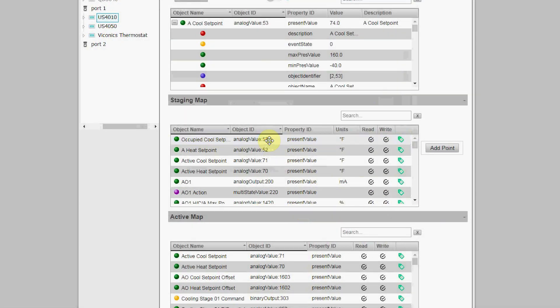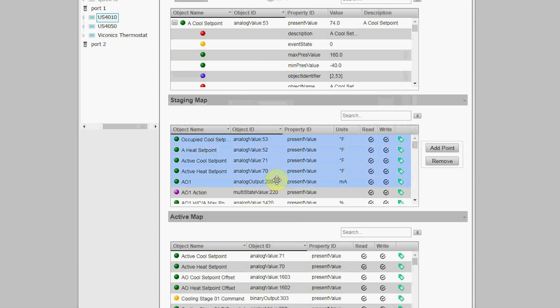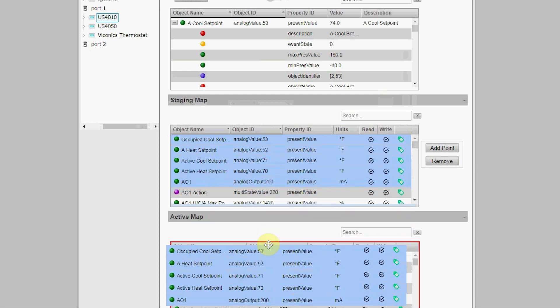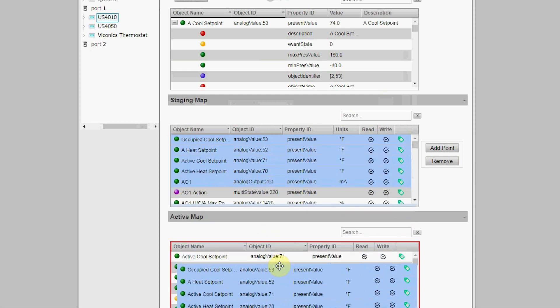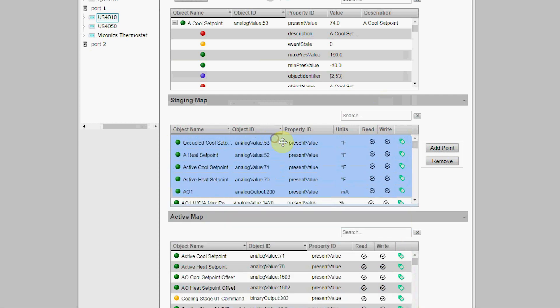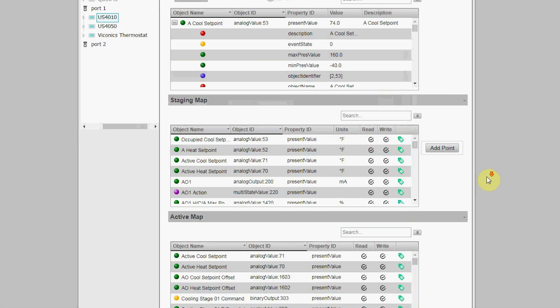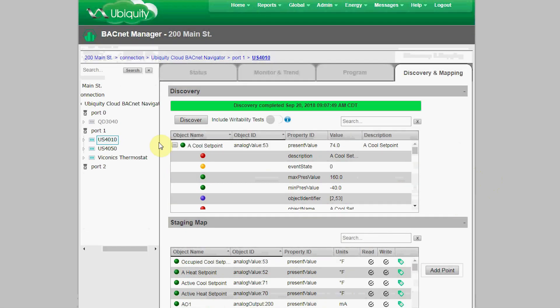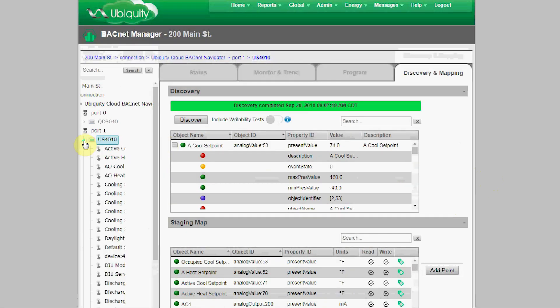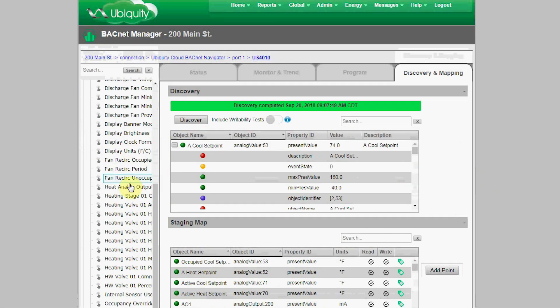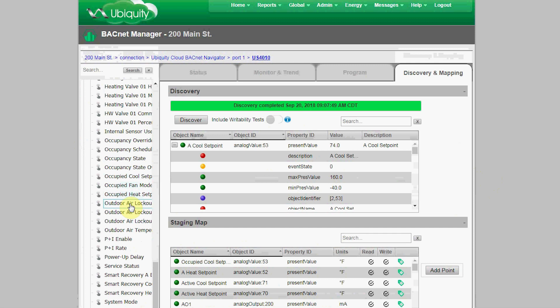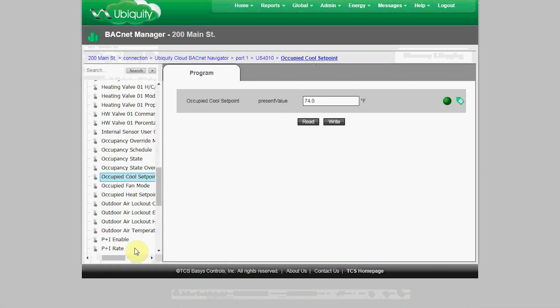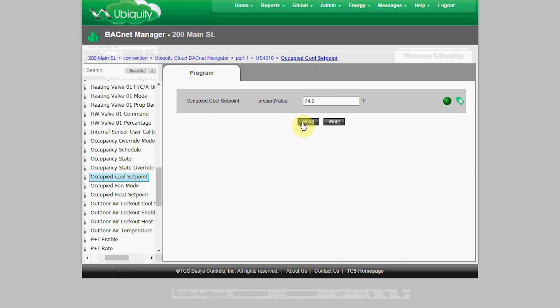Once all the tags are complete, just save the tag editor for this object. Converting these objects to points that can be used in Ubiquity is as easy as simply highlighting then dragging and dropping them into the Active Map. Once they're in the Active Map, you can see each of these points by opening the device on the navigation tree. You can then scroll down to the object we renamed Occupied Cool Setpoint and click on it so you can read the value, check the most recent status, or access the tags.